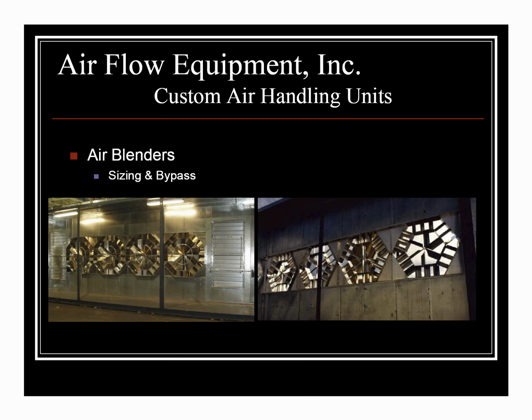But during the cooling season, when the blending is not so necessary and not so critical, this is another situation where you can throw open those bypass dampers, reduce the load on the system, therefore reducing the amount of horsepower needed to run your fan, to save the customer money.